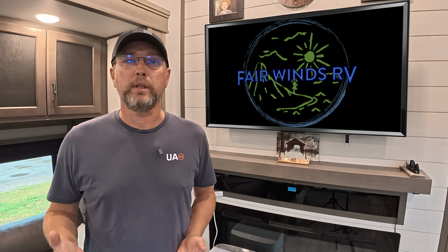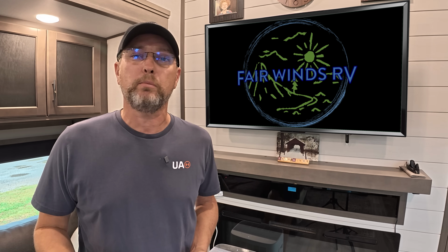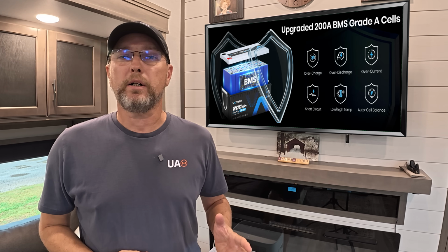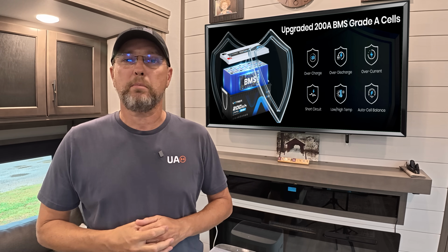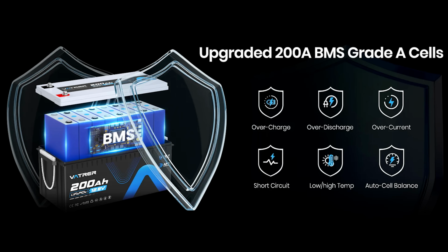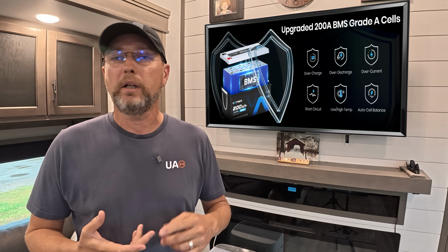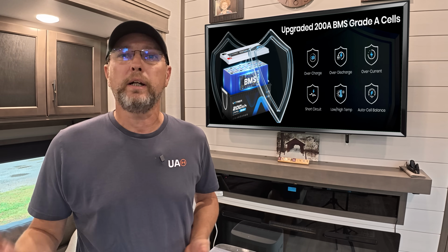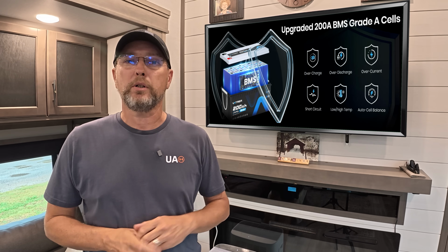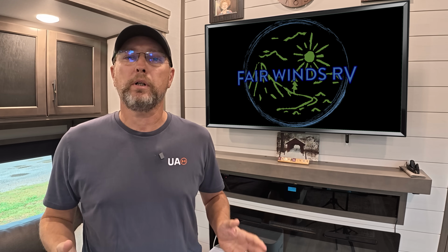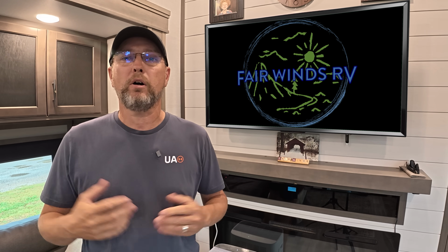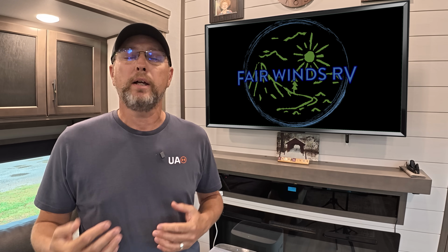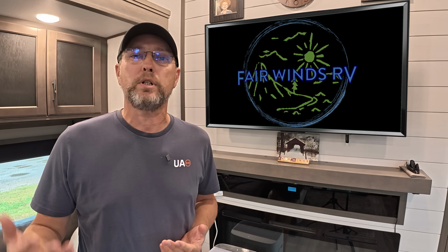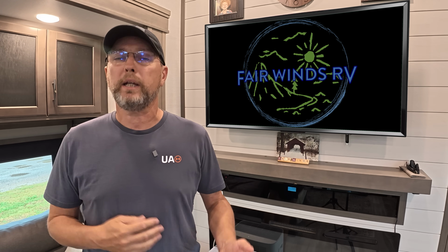But how do we prevent these batteries from even getting to that thermal runaway point? That's where the battery management system, or BMS, comes in. In short, the BMS is the brains of the battery. It's designed to prevent the battery from operating outside its design specifications: high voltage, low voltage, overcurrent, overcharging, overtemp, etc. These systems are mandated by electrical codes and safety standards. So simply put, although lithium iron phosphate batteries are inherently stable and safe, the BMS ensures the battery never gets to a point where it can actually catch fire.